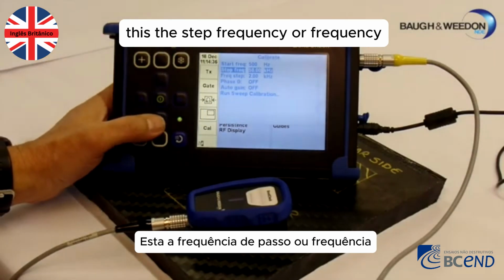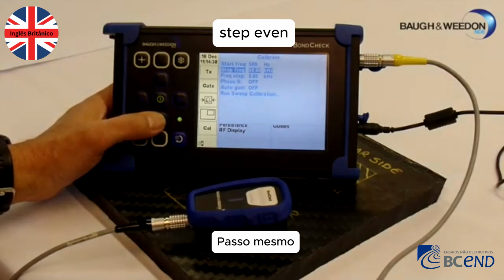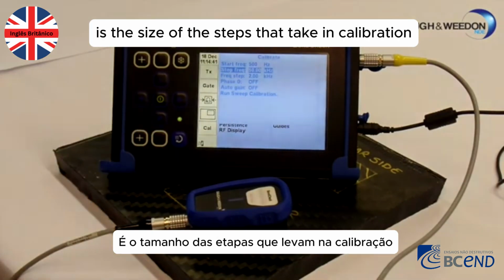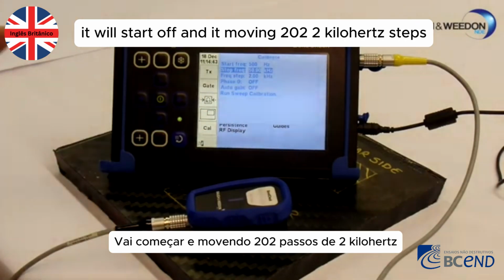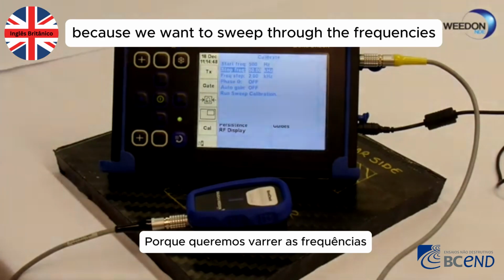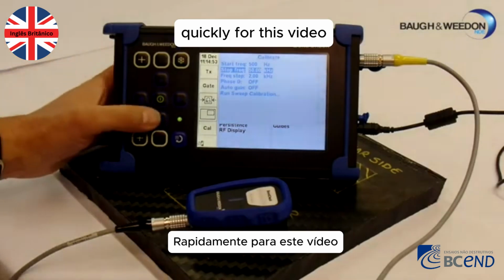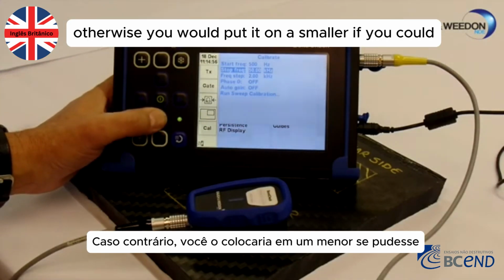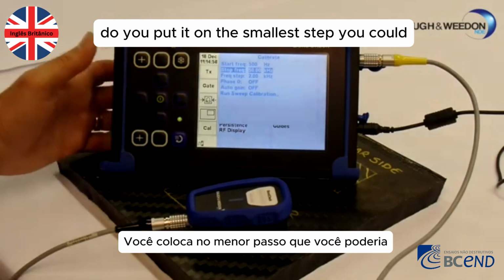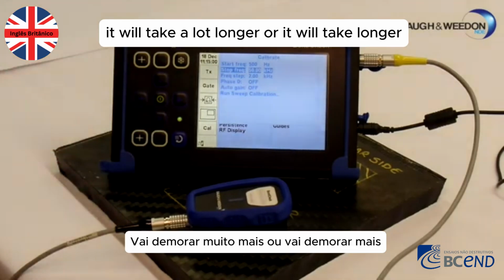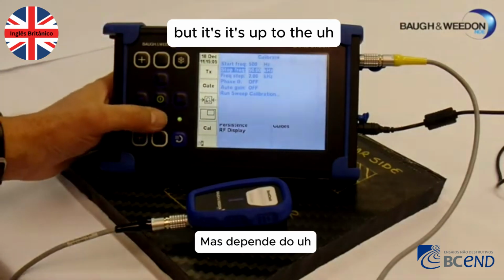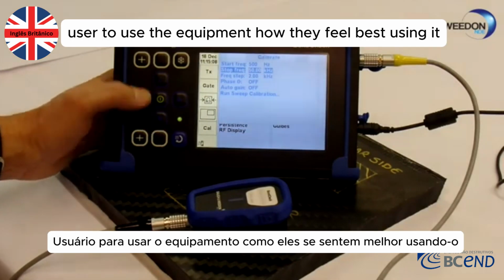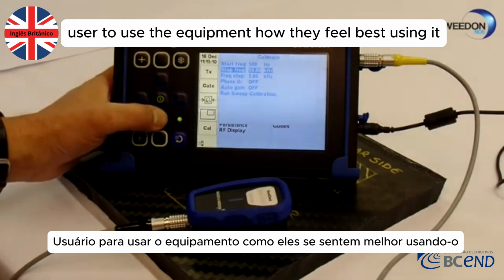Step frequency, or frequency step even, is the size of the steps that are taken in calibration. It will start off and it will move in 2 kilohertz steps. We'll leave it on 2 kilohertz because we want to sweep through the frequencies quickly for this video. Otherwise, you would put it on the smallest step you wanted to. It will take longer, but it's up to the user to use the equipment how they feel best using it.